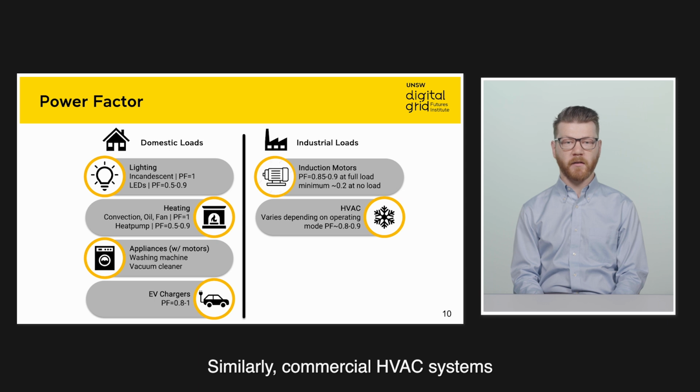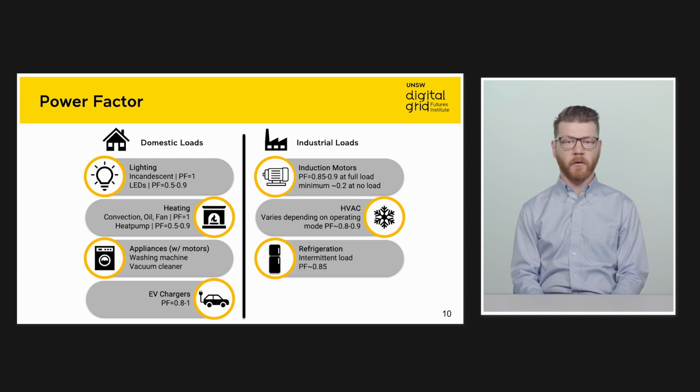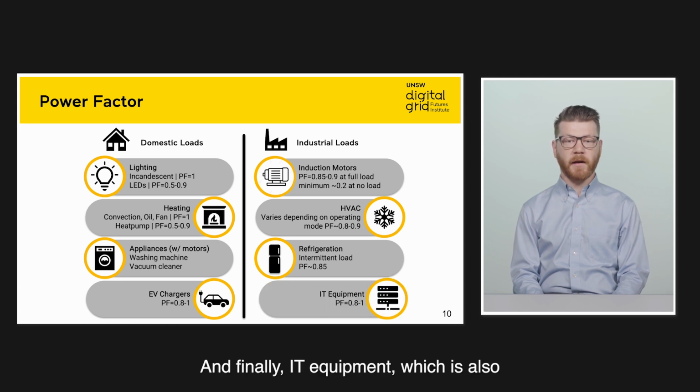Similarly, commercial HVAC systems aren't too dissimilar to your aircon at home, but they're on a much larger scale, and so that low power factor is much more critical. Commercial refrigeration, similarly to HVAC, also presents a relatively low power factor. And finally, IT equipment, which is also doing a conversion from AC to DC power, can present a reasonably low power factor.